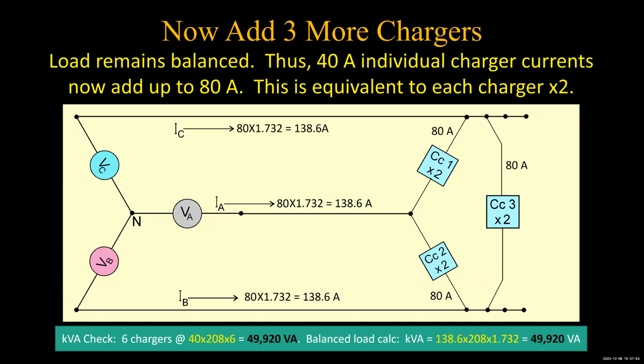And the balanced load calculation says it's 138.6 amps. That's the line current times 208 volts times 1.732. Voila, 49,920 balances out. So the square root of 3 thing comes into play here. And these are line-to-line connections with no neutral anyway. So in this case, you're only going to have 3 wires and a ground wire going through that conduit, and there should be no penalty for 4 wires because there's not supposed to be a neutral anyway with 208 volt chargers. On the other hand, if you have unbalanced 120, or if you have 120 volt chargers that have a lot of third harmonic, then you're going to have some neutral current. So the whole idea is to stay away from the 120s, and then you don't have a neutral to worry about anyway. You've got 3 wires, currents 138.6, and no derate.